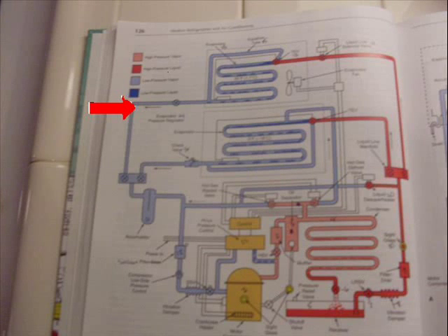On the outlet of the high temperature evaporator is an EPR valve, evaporator pressure regulator. Yes? Are you going to talk about the equalizer? I'll get to it when I get to the second evaporator. But yes, I will. It's one of your parts you can use.